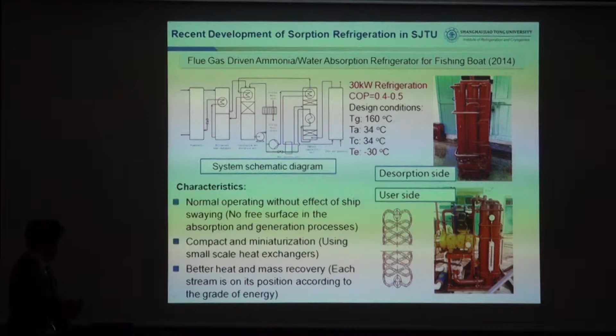So in this case, we had a very specific design for the heat exchangers: we use capillary tube heat exchangers. The inner diameter is about 1.7 millimeter, and it's a stainless steel tube. The heat exchanger uses more than 1,000 meters of tube, so it's very dense with heat transfer surface. Before, we did not have the data, but we made the design and then we succeeded.